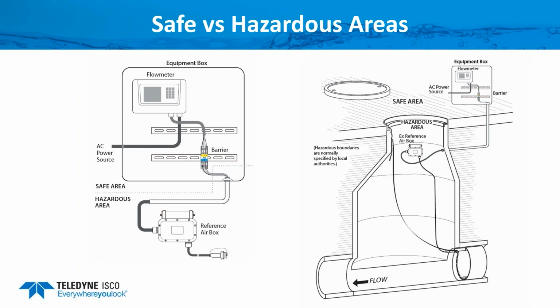Now the other option is the safe versus hazardous areas. This is where you'd have an intrinsically safe sensor that you put in the classified area, and then you have a non-rated controller in the safe area. What we're looking at here is that down below on the right, the sensor is in the classified area. And whenever you have a pressure transducer, it needs to be vented to atmosphere in the hazardous area. So that's why we're showing here an air reference box. So it vents to atmospheric pressure in the hazardous area. And then the cable that's attached to it is a sealed cable. So that way, even if the cable was cut, we're not going to allow any of the gases to transmit through the air reference line. And so you'd run it through a conduit, which should also be sealed, and goes to an IS barrier.